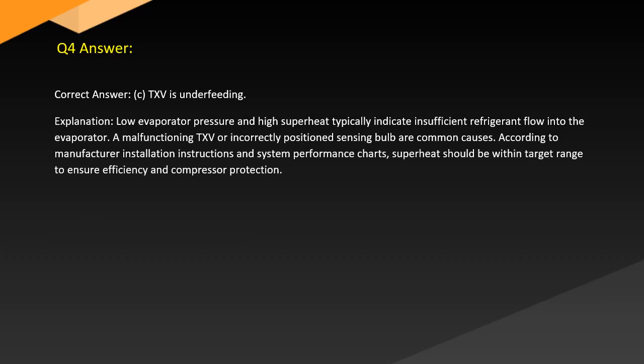Answer. Correct answer, C. TXV is underfeeding. Explanation. Low evaporator pressure and high superheat typically indicate insufficient refrigerant flow into the evaporator. A malfunctioning TXV or incorrectly positioned sensing bulb are common causes. According to manufacturer installation instructions and system performance charts, superheat should be within target range to ensure efficiency and compressor protection.